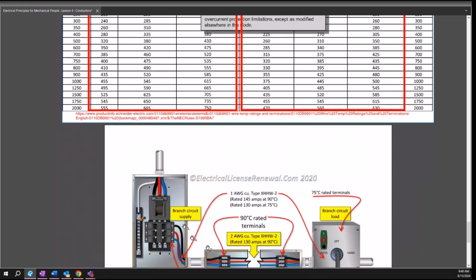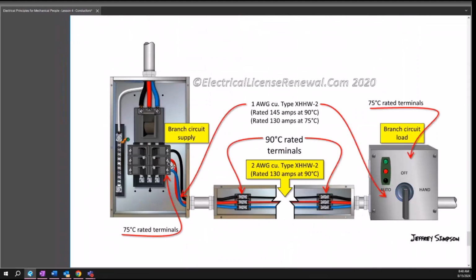Yeah. Cool. One way we can actually get around that is 75C conductors to 90C. And then between these two 90C conductors, you can actually decrease the conductor size because it's rated for more amps. These terminations aren't going to melt at anything lower than 90C. I've actually done this when you get 100, 200 foot runs of something. It just makes better sense to hit 90C conductors, run at 100 foot, hit 90C conductors again, and then go into whatever the load is. Or even if your load is rated for 90C, great, you don't even have to hit the second set of terminations.